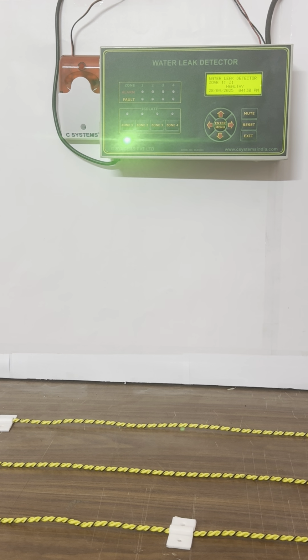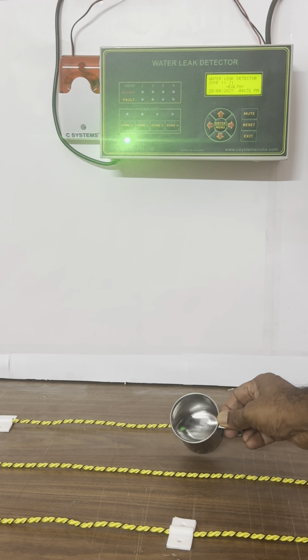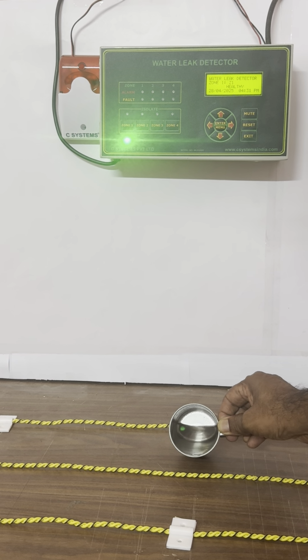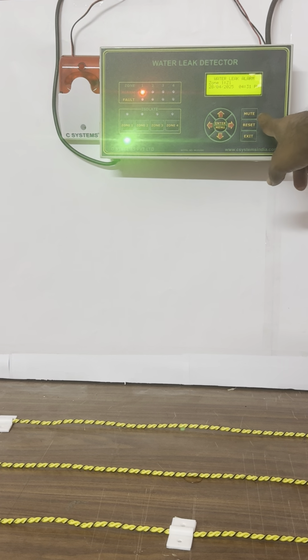Now I am going to demonstrate the water leak detection system in alarm condition by putting water on the sensor cable. The moment water touches the sensor cable, we will get the alarm displayed on the display as well as in the zone indication. Along with it, the hooter and strobe will also get activated. Once the alarm is generated, I will press mute and then continue the demonstration, as it will be very loud and you will not be able to hear it properly. You can see that I have dropped only one drop of water on the sensor cable. The alarm is immediately triggered.